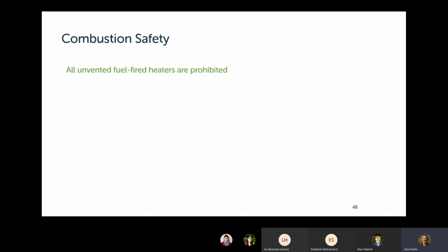The most common form of these is what's called a vent-free fireplace. So a manufactured unit looks like a fireplace, burns gas, and is specifically designed to dump 100% of the combustion gases into the living space 100% of the time. Those are not allowed in Vermont, in residences.